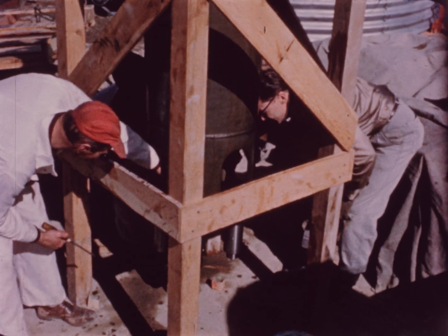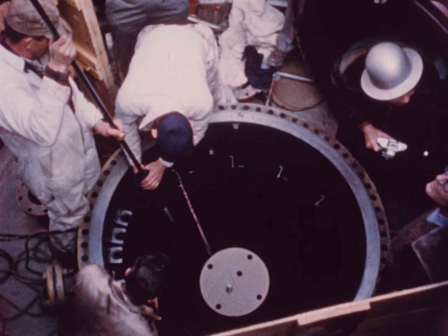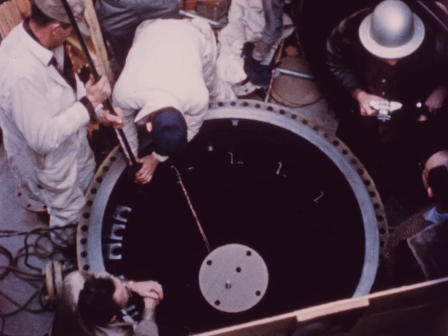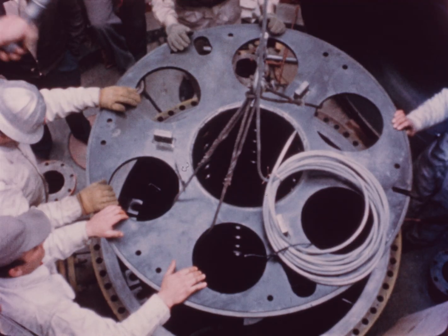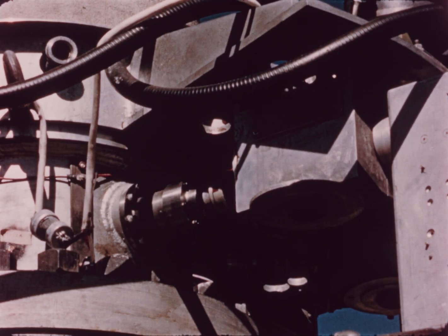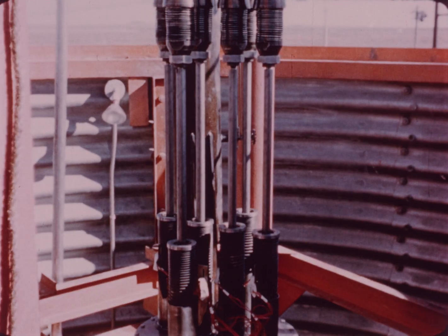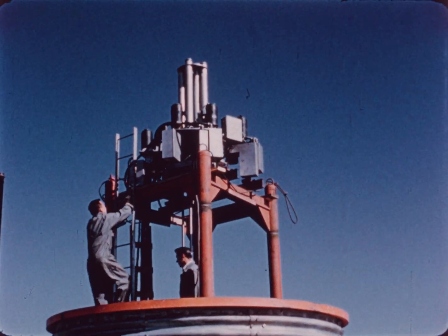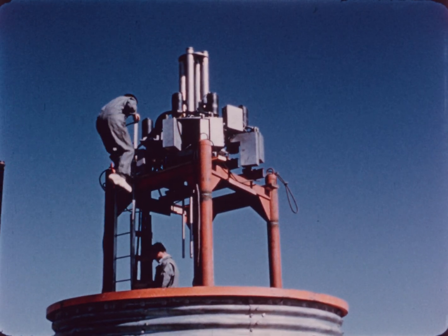After placing the grid plate and control rod structures in the core tank, their assembly began. The rod damper cylinders were attached to a suitable bridge, then inserted into the core tank. The six control rod locking devices were then connected and the rods were attached. The damper cylinder bridge was lowered into its proper position. A rack and pinion system is used to move the rods during reactor operation, and a spring trigger system is used for rapid insertion in emergencies. Each locking device is connected to a piston that cushions the rods in the cylinders.